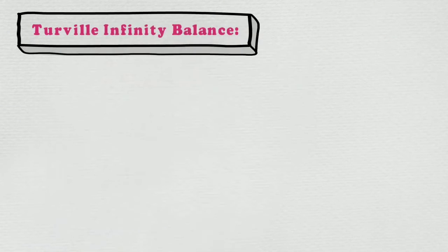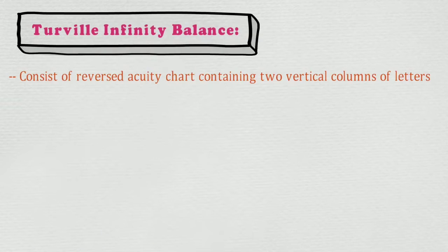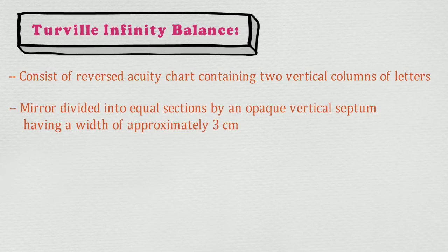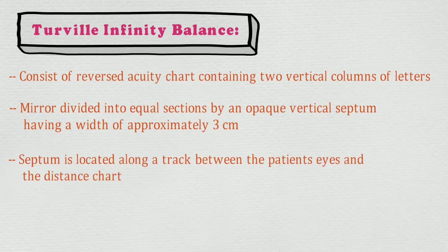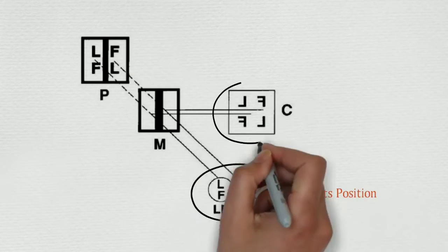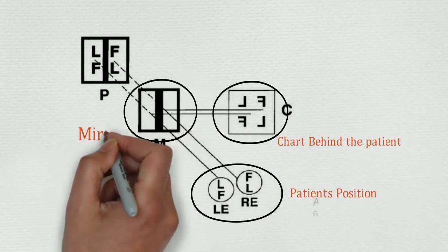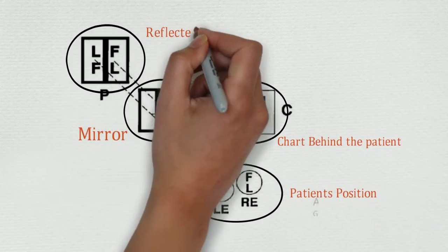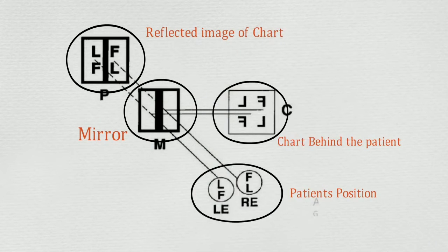The Turville Infinity Balance Test consists of a reversed acuity chart containing two vertical columns of letters, divided into equal sections by an opaque vertical septum having a width of approximately 3 cm. The septum is located along a track between the patient's eye and the distance chart. In this figure, the patient position, the chart behind the patient, the mirror, and the reflected image of the chart are shown.